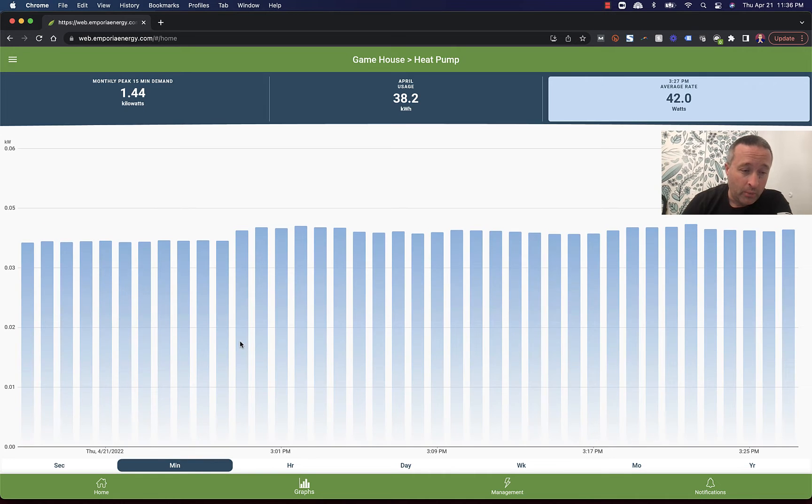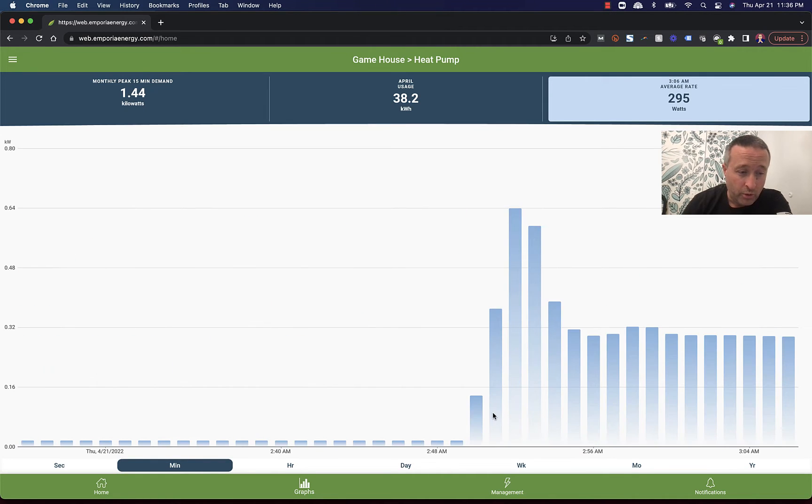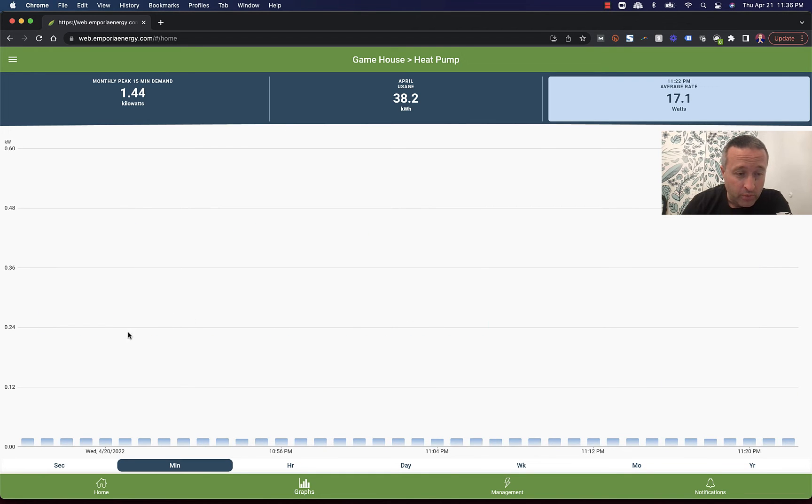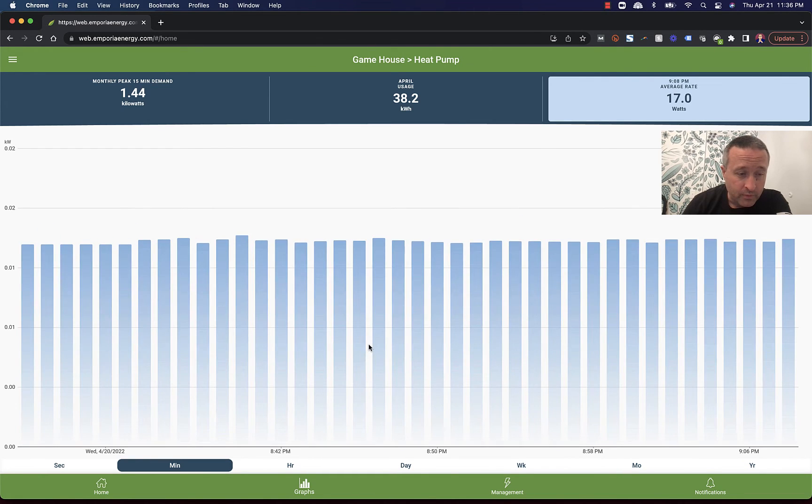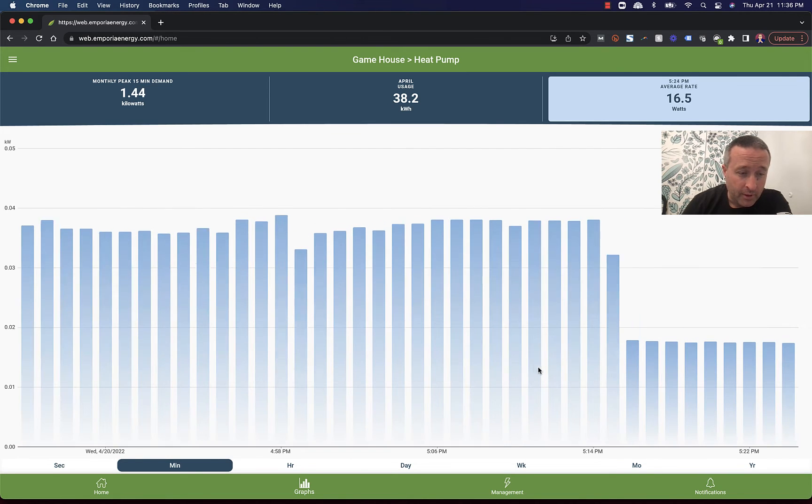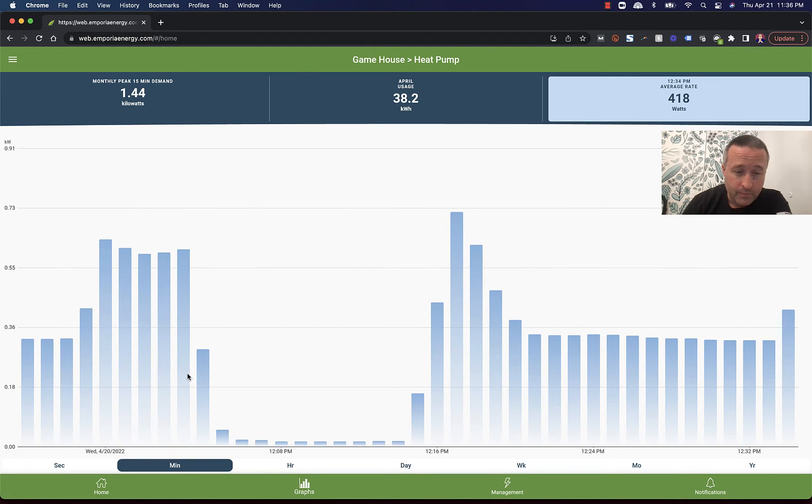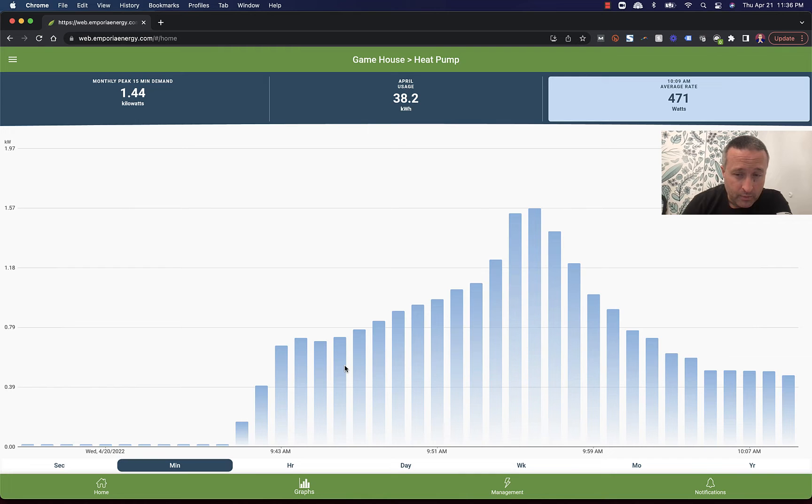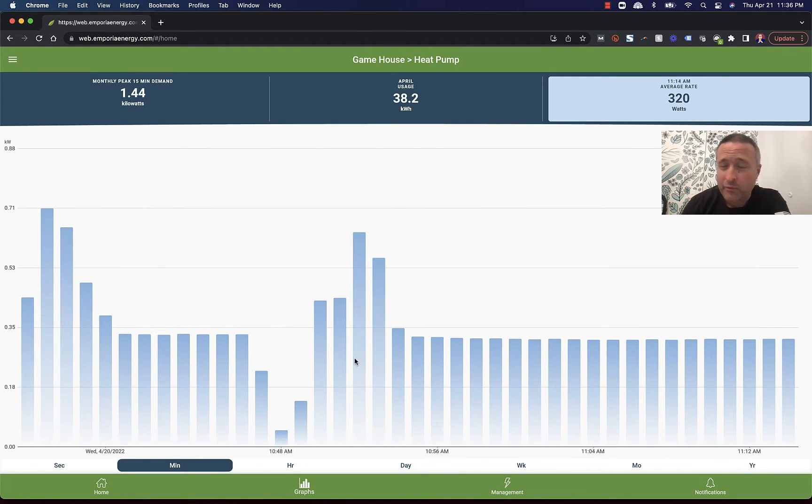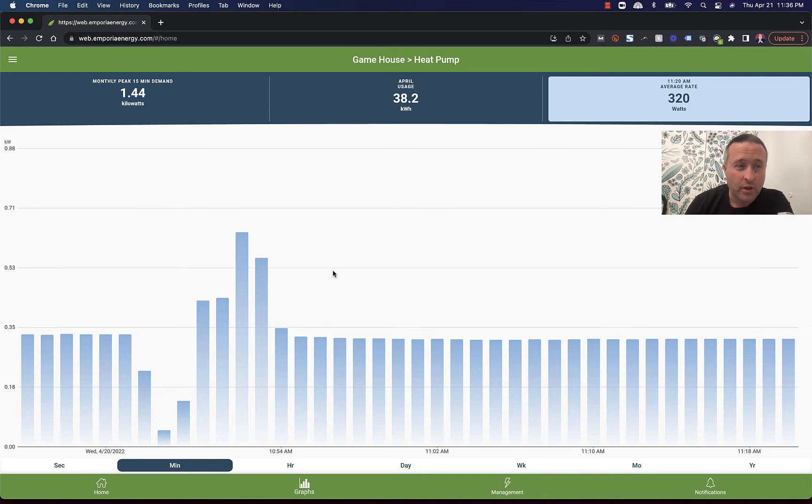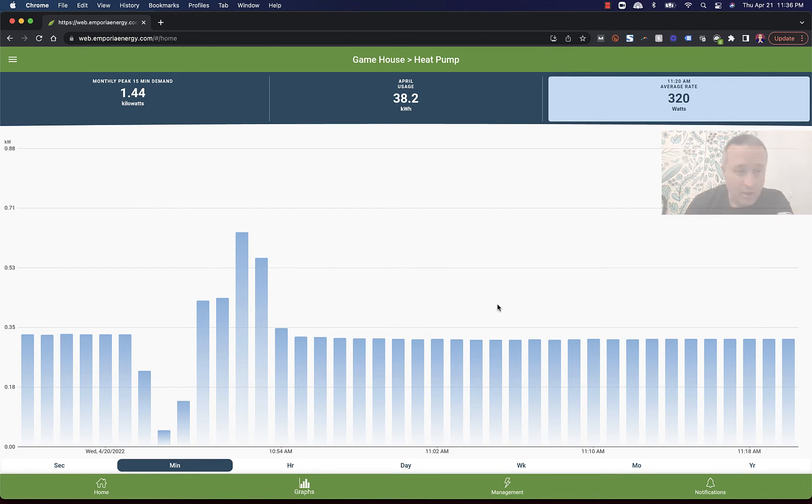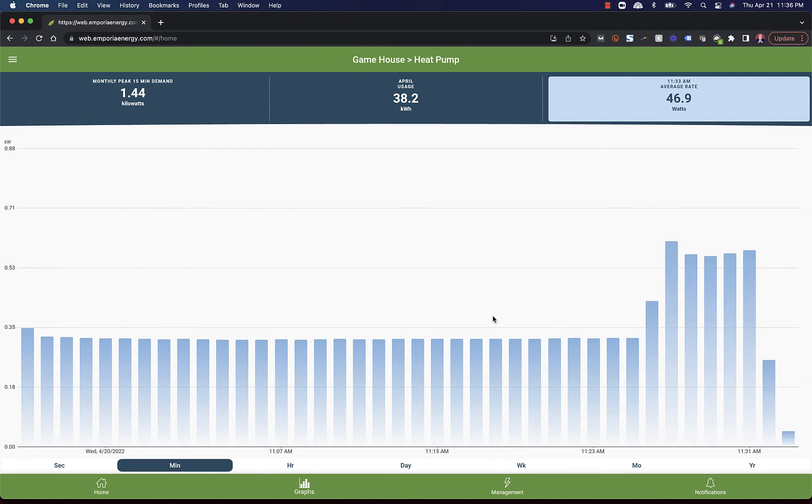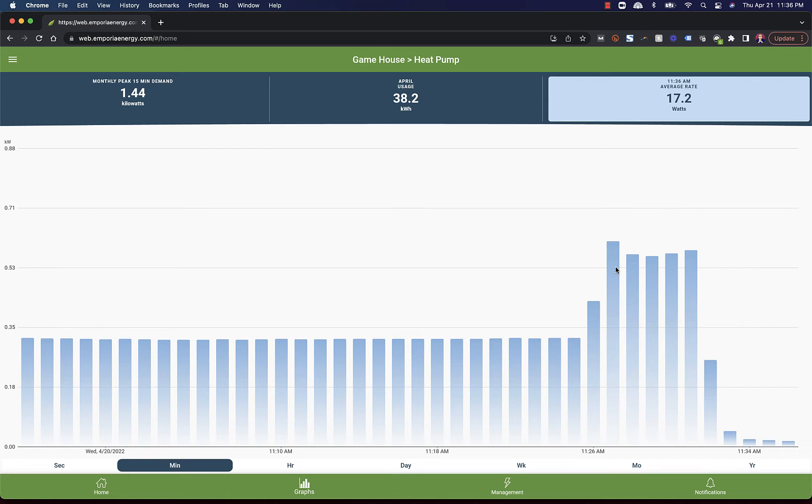Dang it. So I may have hit the end of what it will show me. Oh yeah. Well, so here you go. It was about freezing. And it's going to be 80 degrees here this weekend. We had snow last weekend and then 80 degrees this weekend. But here it is running again. 320 watts. Look how nice and long this cycle is. And it's got a similar pattern. So it runs at that low level for a long time and then decides, okay, we need to kick it up a little bit to get it to satisfy. And then it shuts off a few minutes later.